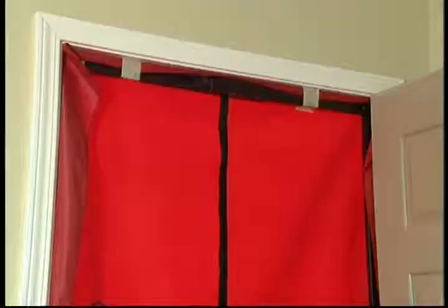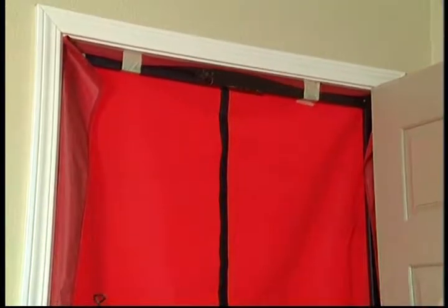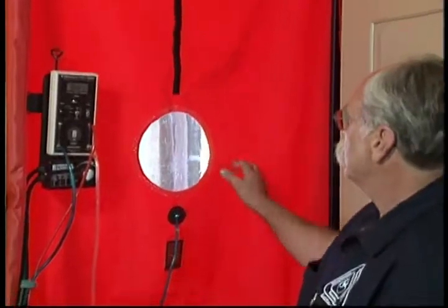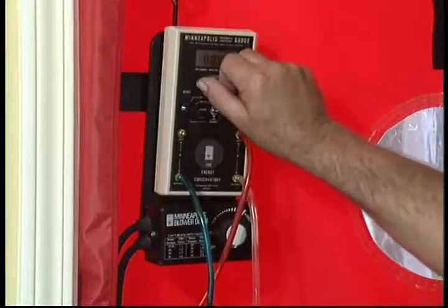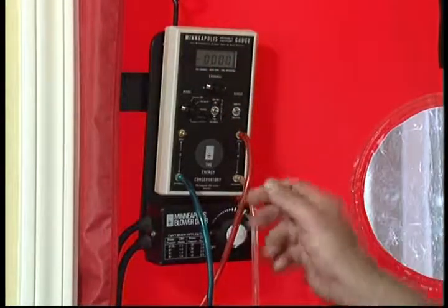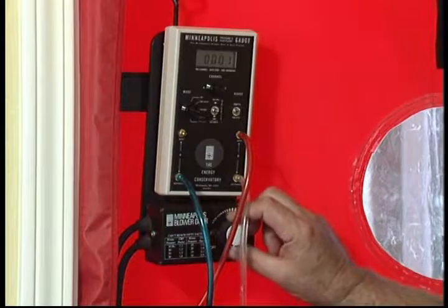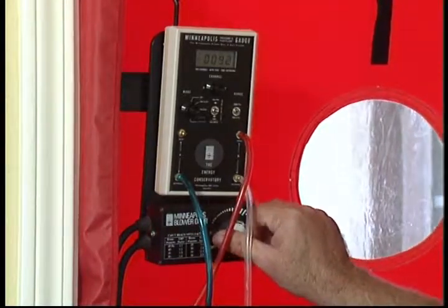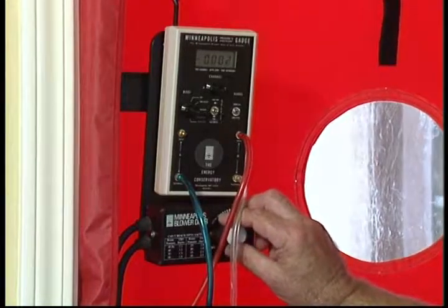And here to tell us how a blower door works is Scott Johnson from Action Now. Hi, Scott. How you doing, Steve? Well, tell me about the blower door and how it works and how you prep to make it work. A blower door is a simple piece of equipment. It's comprised of a frame and a membrane and a fan and a manometer and a speed control. Those tubes coming out of the manometer that hook up into the fan and go to the outside are our reference taps to let us know really what's going on with pressures and the airflow itself.